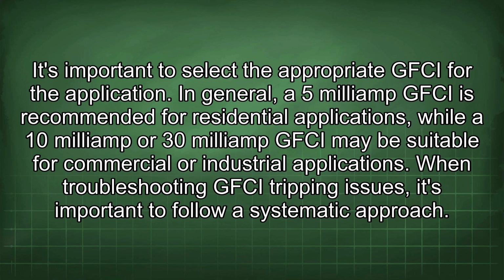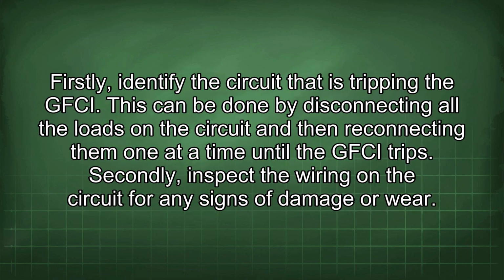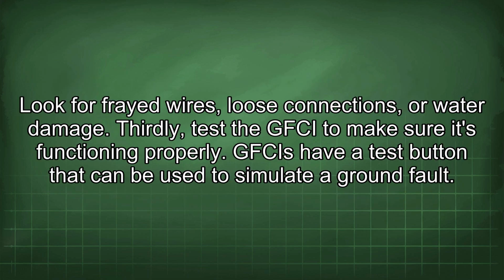When troubleshooting GFCI tripping issues, it's important to follow a systematic approach. Firstly, identify the circuit that is tripping the GFCI. This can be done by disconnecting all the loads on the circuit and then reconnecting them one at a time until the GFCI trips. Secondly, inspect the wiring on the circuit for any signs of damage or wear. Look for frayed wires, loose connections, or water damage.